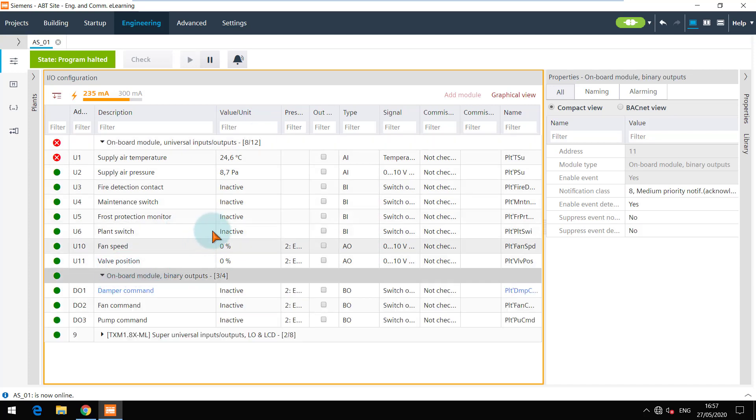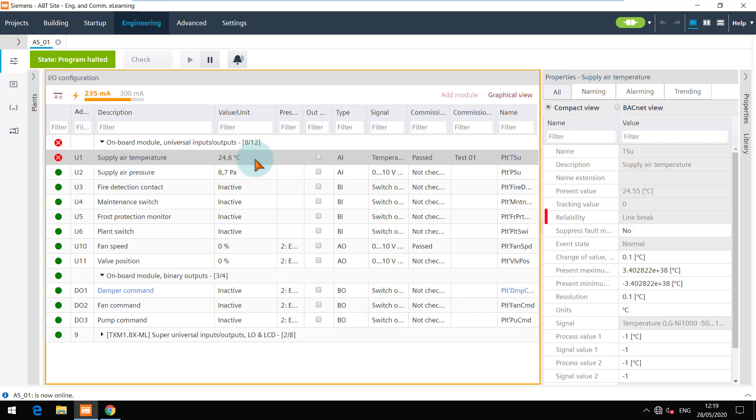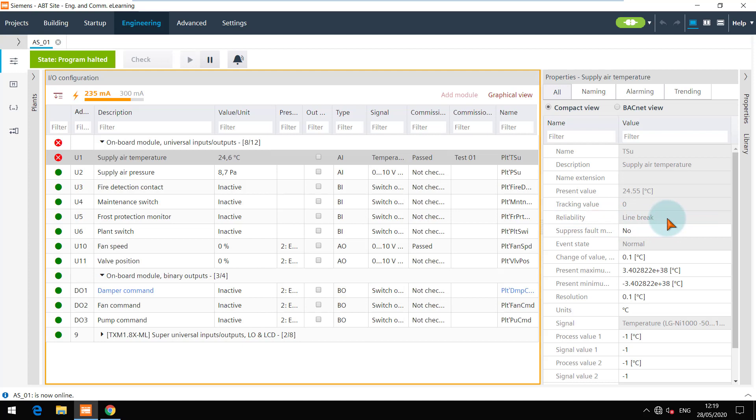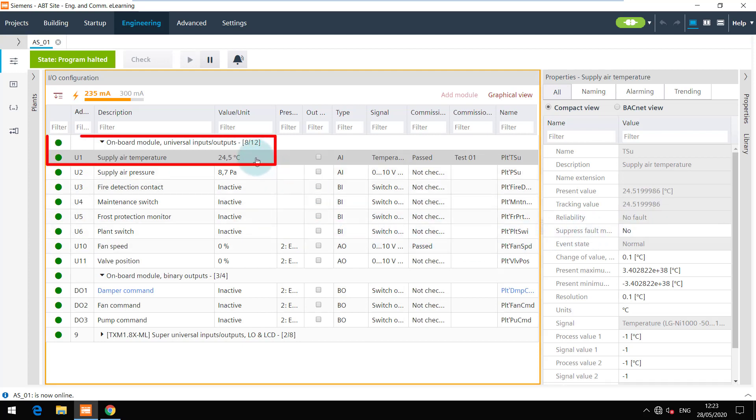We see that there is a problem with supply air temperature, and the reliability in the properties shows that the line is broken. Let me check it on my setup. And yes, I found the break. I fixed it and now the status here is also updated. There is no fault anymore.